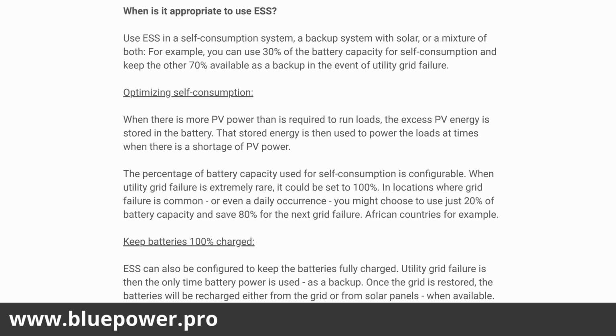The other option, how you can run the system, is to keep batteries charged. So what that will do is just feed your loads from PV power, and the rest will be throttled if you do not feed in your excess PV power. So your battery will be kept at 100% unless there's a power failure.